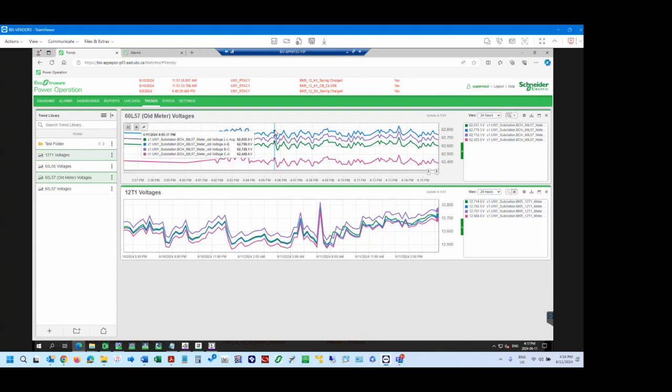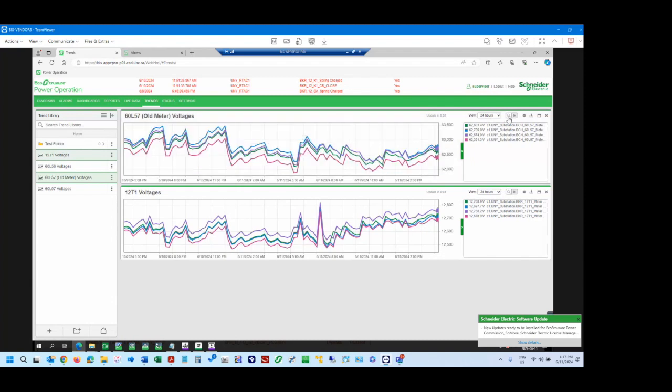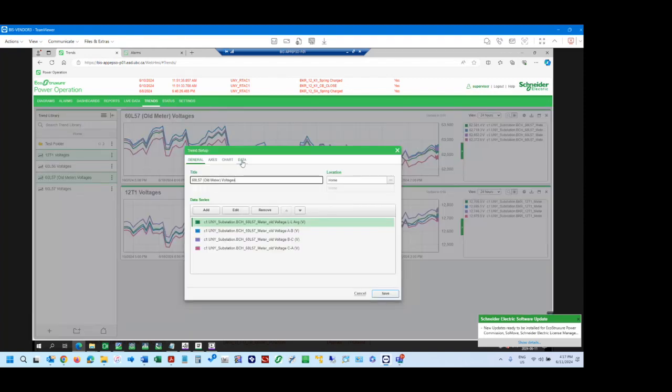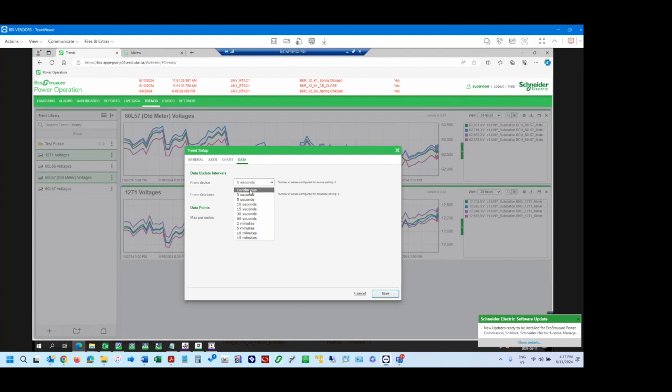So let's say you wanted to do a test, and you wanted to really look at it live as you were doing the switching. You could set this up to watch for what you wanted to watch for, and then say go, and you would be able to see down to 1 second resolution. So it can be used for real-time investigation, up to 1 second. Continuous is basically as fast as 1 second.